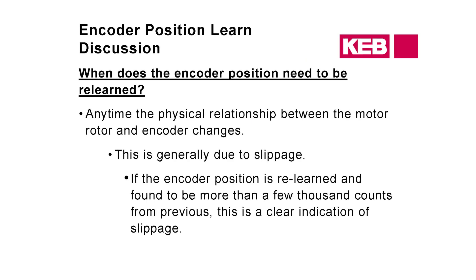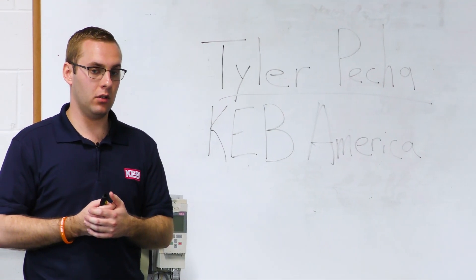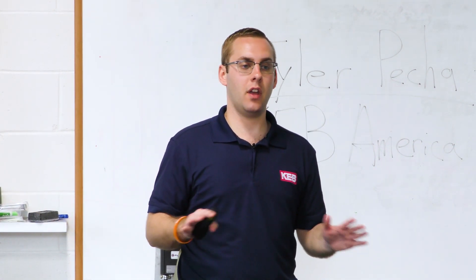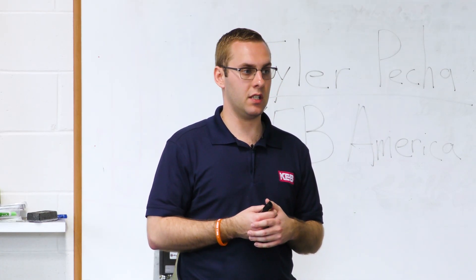Other than startup, when would you have to do another SPI? Anytime the encoder has been taken off or moved — even if someone just bumped it while working nearby, you might have to do another one. The encoder position and mounting are absolutely critical for proper operation of the permanent magnet motors. Once the correct position has been learned and the motor is running, there's no need to change anything, and that goes for both mounting of the encoder and switching the channel phasing.